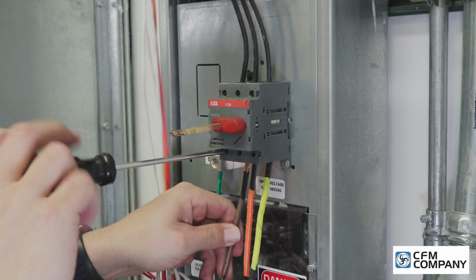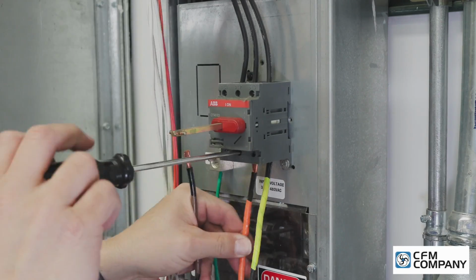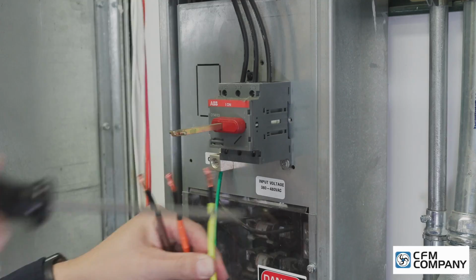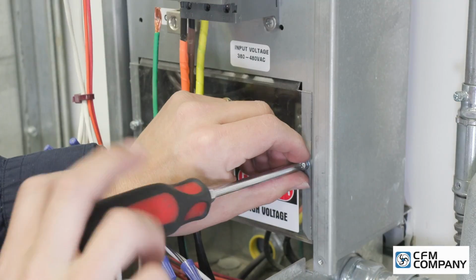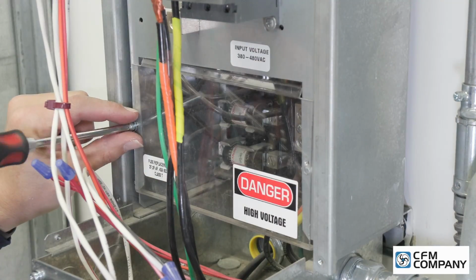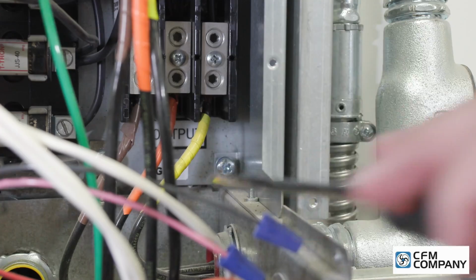Starting at the main disconnect, the line side power wires are removed. The plastic access shield must be removed. There are two No. 3 Phillips head screws in the lower corners that hold the front disconnect plate to the enclosure. Remove the screw on the lower right by the motor terminal block. Remove the screw on the lower left by the drive input fuse block.